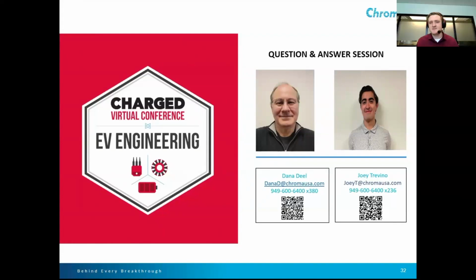The next question is, what's the minimum input voltage required to operate the unit? Our units differ per unit, but generally they operate at either three-phase 120, 208, or three-phase 480. Generally at three-phase 208, some of the units derate, so that could be two-thirds power or 80% power. It depends on the unit, so it's good to check with us beforehand to validate that the power is good.